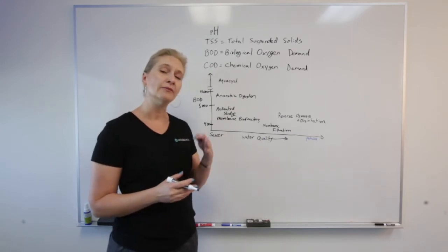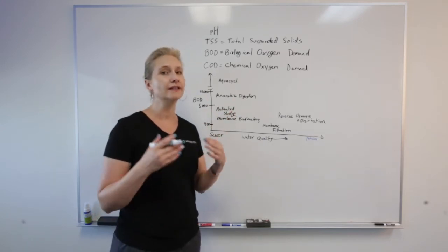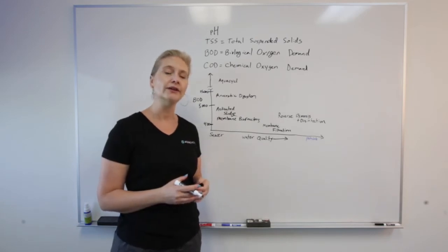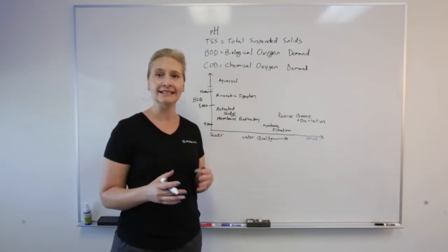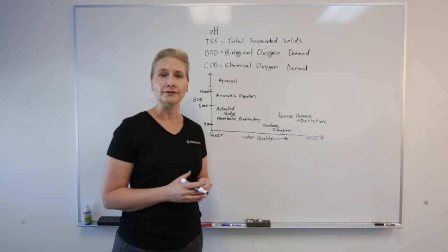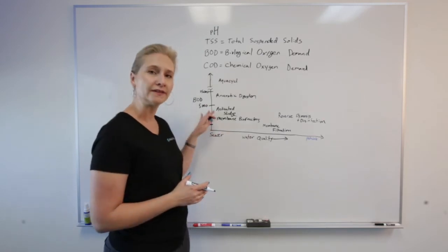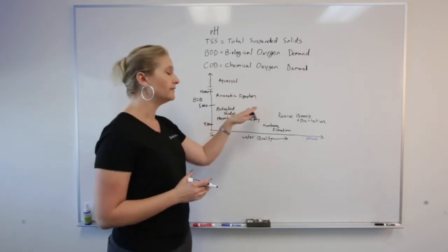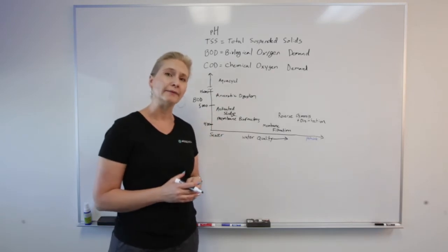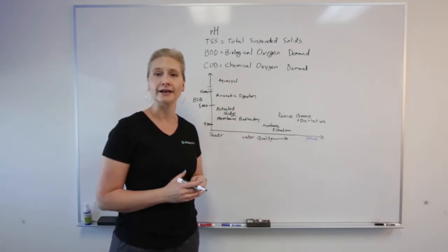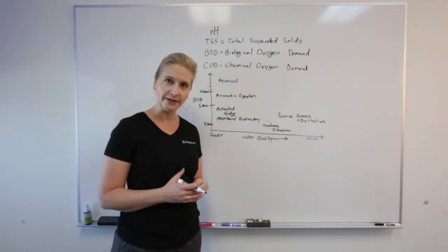That anaerobic process can take much higher concentrations, but it's going to be slower to treat. So you have to plan for at least a day, if not longer in a treatment time, whereas the aerobic processes are usually much faster. You still have a pretty considerable energy requirement here if you're not capturing that biogas and reusing it to offset the operational cost.